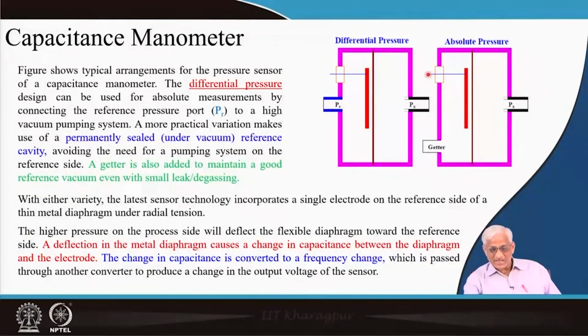So this fixed electrode and this variable electrode diaphragm bends based on the local pressure value, which can be 100 millibar, 1000 millibar maximum, or 1 millibar. Different ranges will have different diaphragms. You will not use one diaphragm for the entire range, maybe 1000 to 100 one capacitance gauge, 100 to 10, 10 to 1. Several manufacturers manufacture these things.